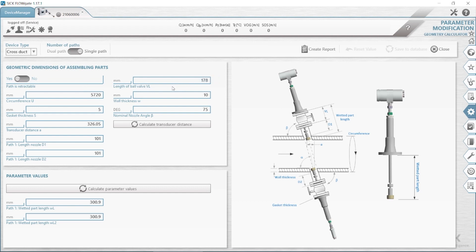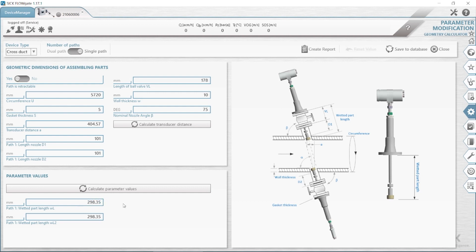Here we will insert our measured dimensions — for instance, the length of the ball-valve, our wall thickness, the nominal nozzle angle beta, our circumference of the pipeline. In this example, we will use a 72-inch pipeline or DN1800, our gasket thickness, and also the length of our nozzles. We will click on 'Calculate Transducer Distance', and now we have to click on 'Calculate Parameter Values'. Now the system has calculated our wetted path length. Please check those lengths for their plausibility. Write the wetted path length down, because we will need it later for the mechanical adjustment.